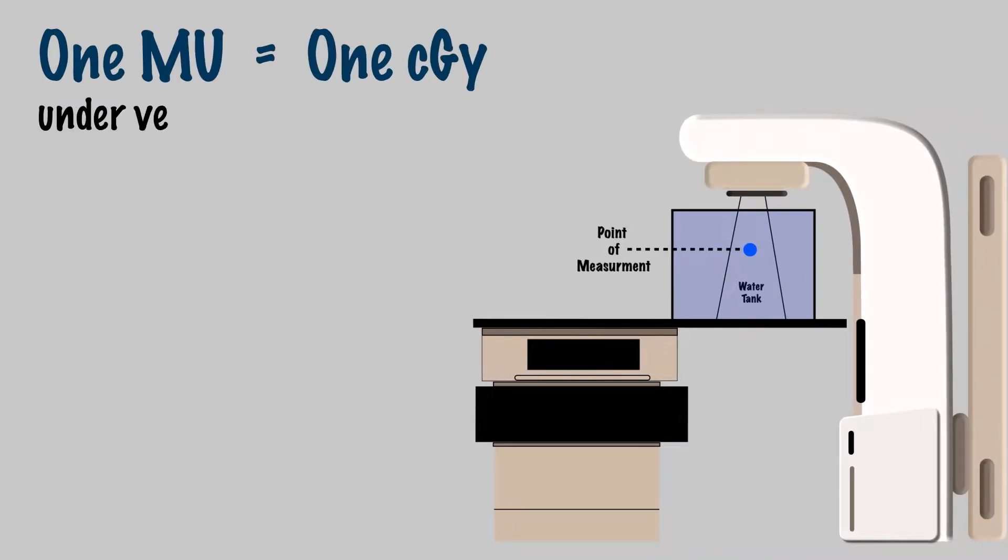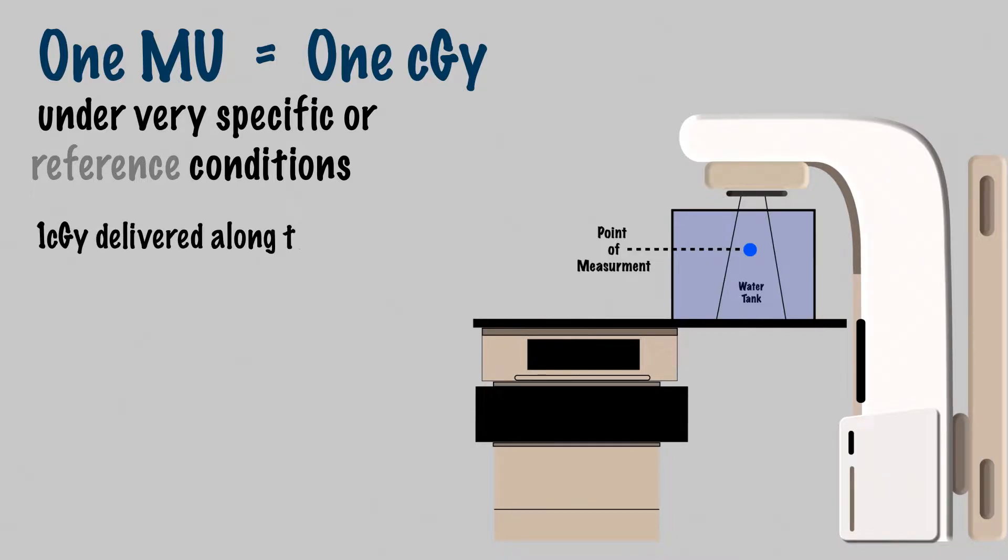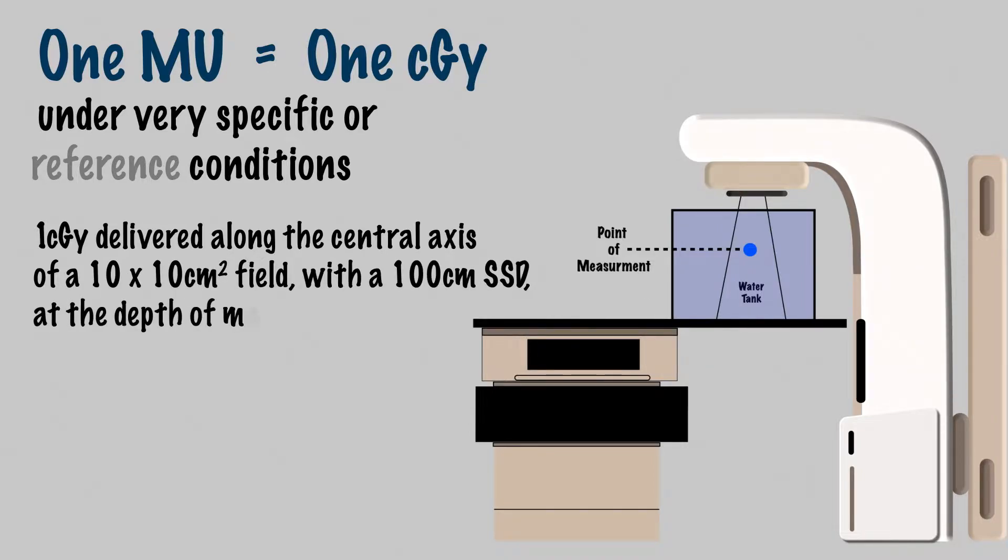First off, what exactly is a monitor unit? Well, one monitor unit equals one centigray under very specific or reference conditions. Let's assume that your clinic uses the typical reference conditions and defines a monitor unit to be one centigray delivered along the central axis of a 10 by 10 centimeter field with a 100 centimeter SSD at the depth of maximum dose, which we call D-max. When we prescribe a particular dose in centigray, it is ultimately delivered by the LINAC in monitor units.